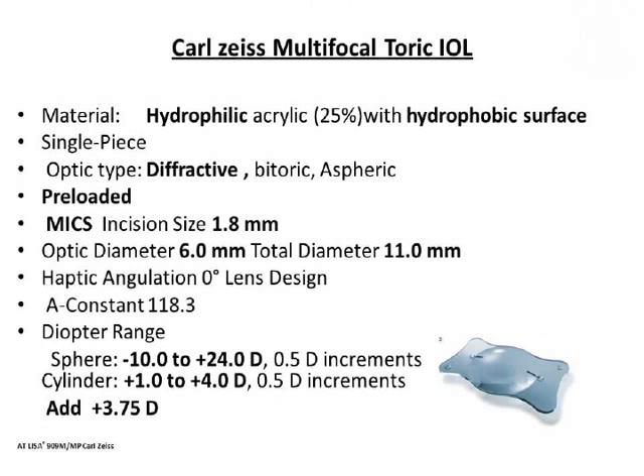The Carl Zeiss multifocal toric IOL is a hydrophilic intraocular lens with a hydrophobic surface. It is a diffractive IOL that is pre-loaded and can be implanted through a 1.8mm incision. The optic diameter is 6mm and total diameter is 11mm. It is available from −10 to +24 diopters in 0.5 diopter increments in the spherical range, and +1 to +4 diopters in the cylinder. This IOL has an add power of +3.75 diopters for near.